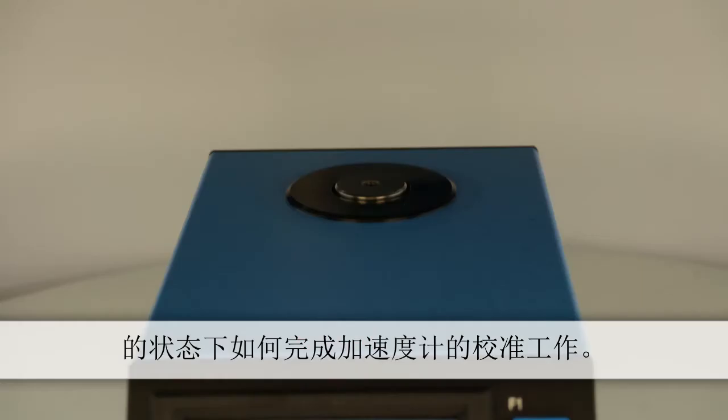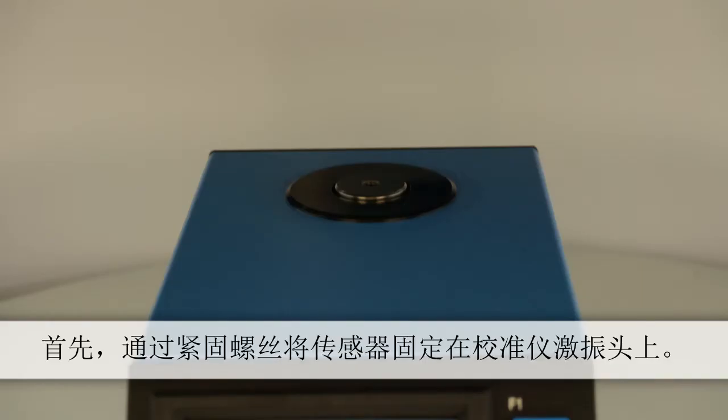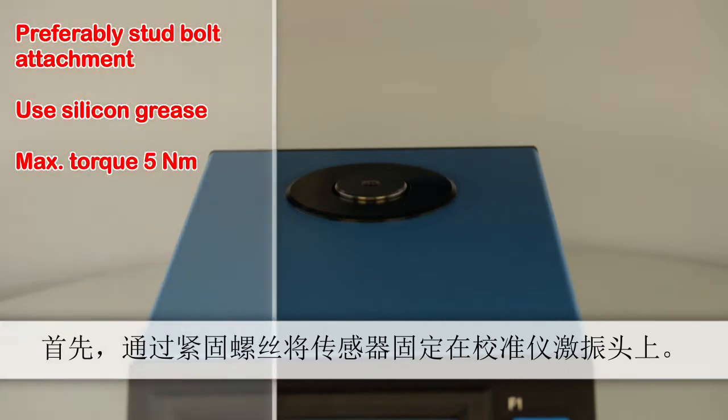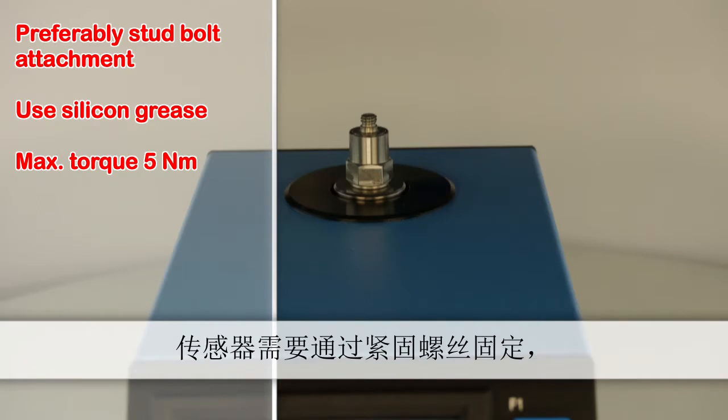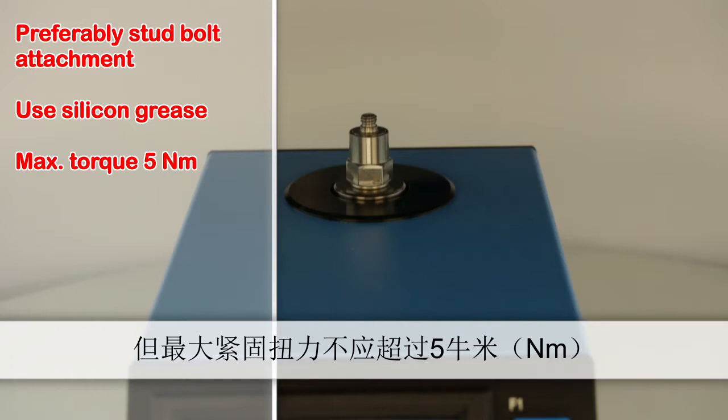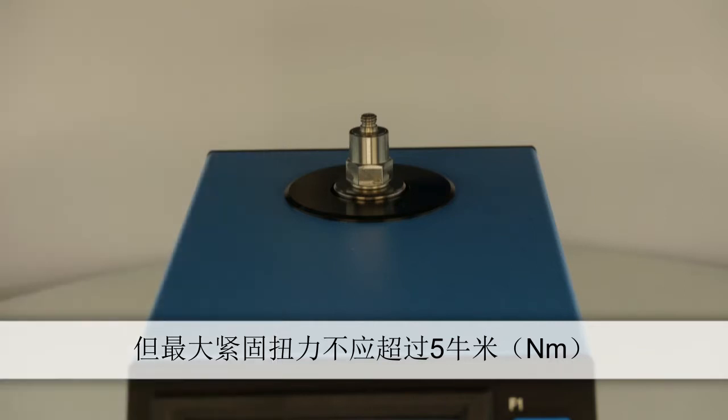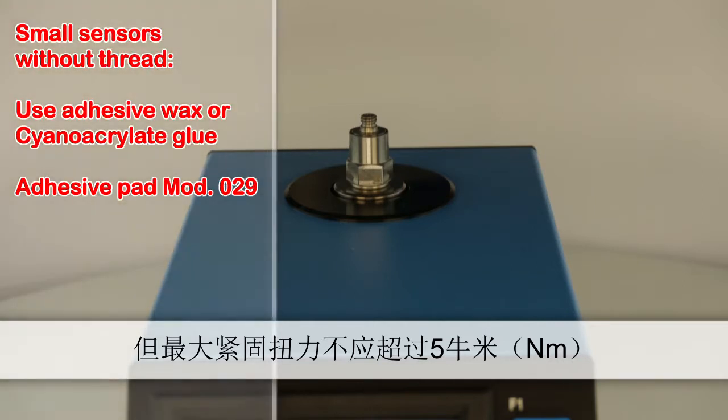Now we'll demonstrate how to calibrate an accelerometer without connecting to a PC. First, screw the sensor onto the vibration shaker using a stud bolt or thread adapter. The coupling surface should be lubricated with silicone grease to improve transmission. The sensor needs to be screwed on tightly, however the torque should not exceed 5Nm.